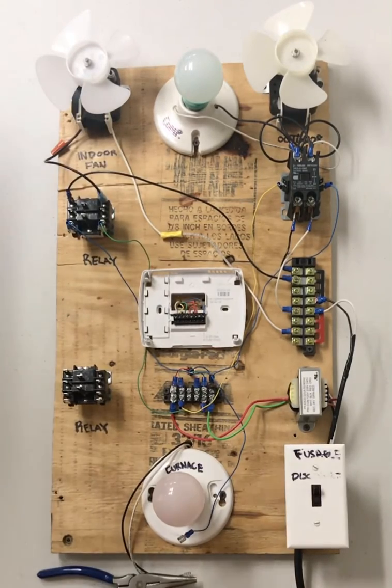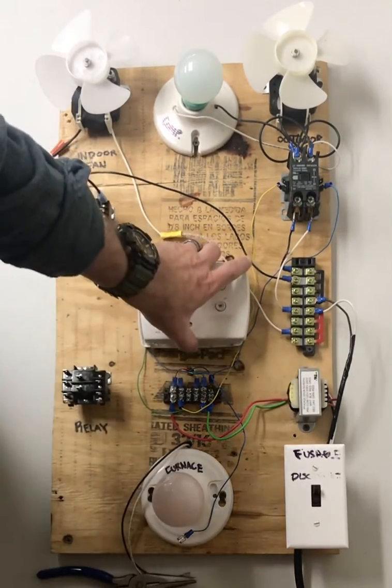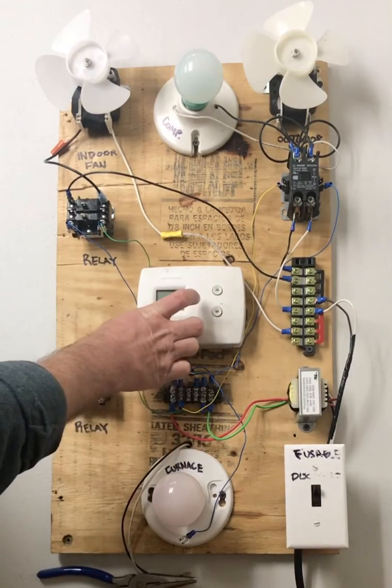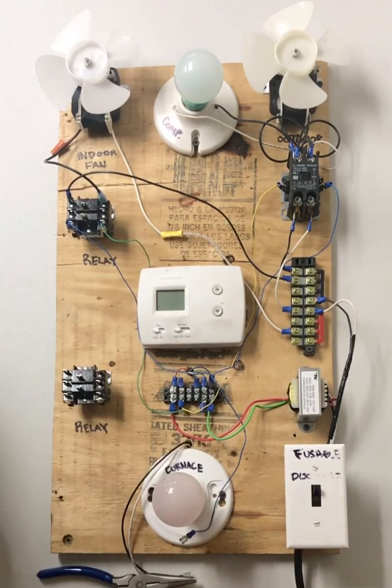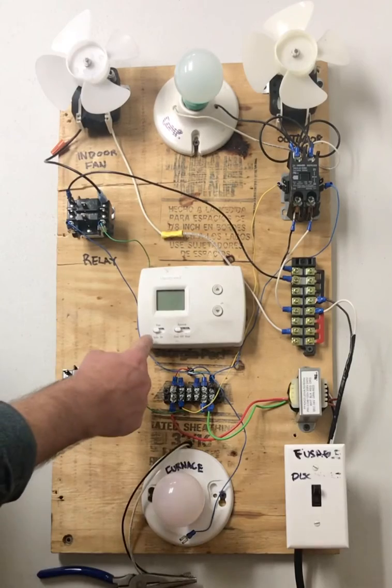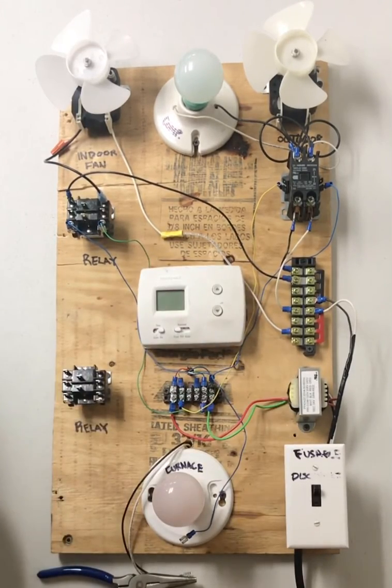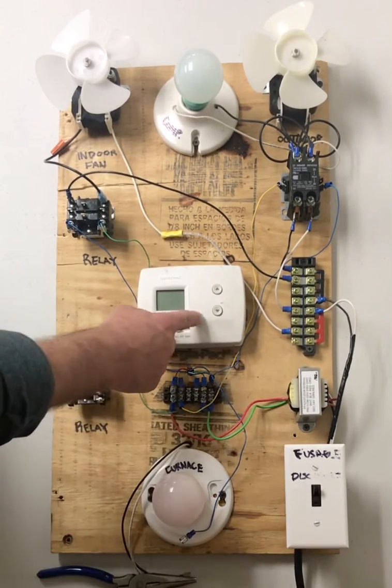So if you had a customer call in and say, hey, I'm trying to run my air conditioning here and nothing's happening, and you get over there and you see that indeed the thermostat's set to cool and nothing's going on. Well, one way you can determine whether you've got a bad thermostat is you can jumper the thermostat. Now, the first thing I would do is I would switch the fan to on. And if I still get nothing, then I'm thinking, well, the first thing I'm going to check is going to be the easiest, which is going to be this thermostat.